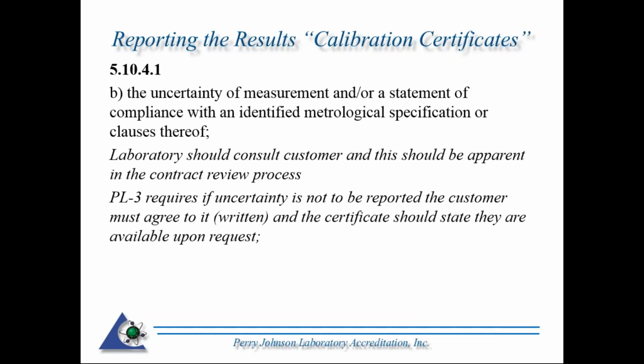Okay, here's a big one here, 5.10.4.1. The uncertainty measurement and/or a statement of compliance with identified metrological specification or clauses thereof. So here's where a little bit of the confusion comes into play. It states the uncertainty and/or a statement of compliance. So there's some leeway there.